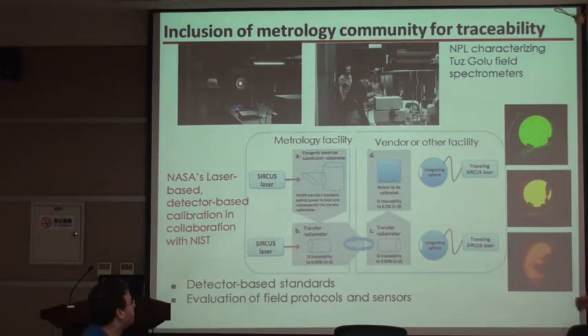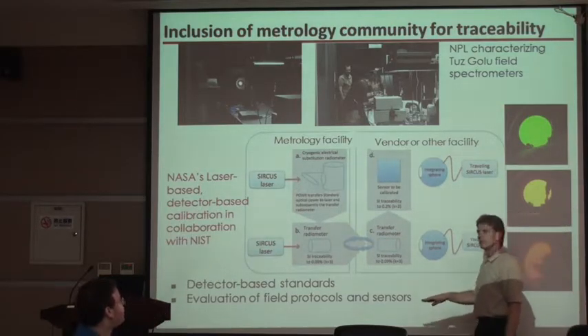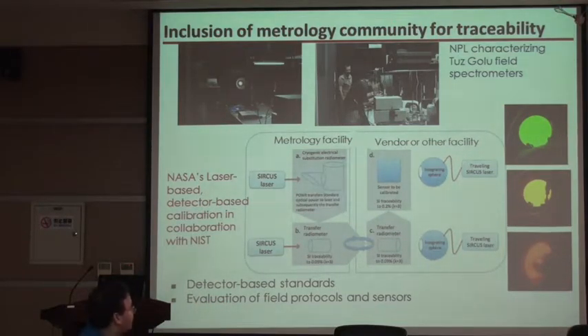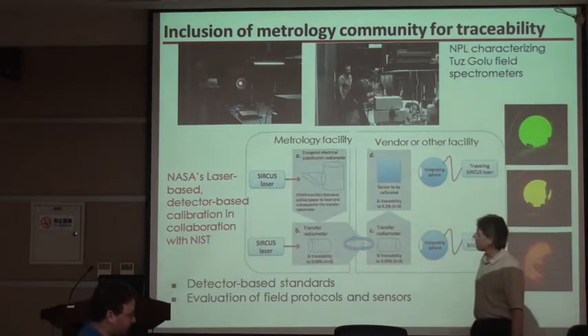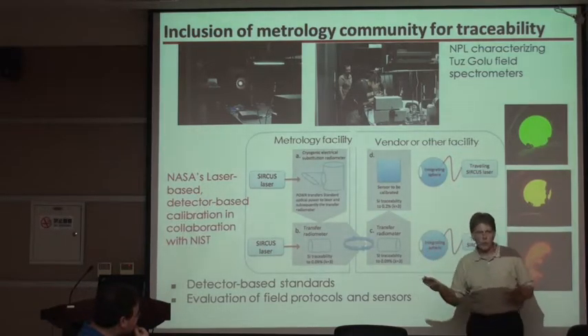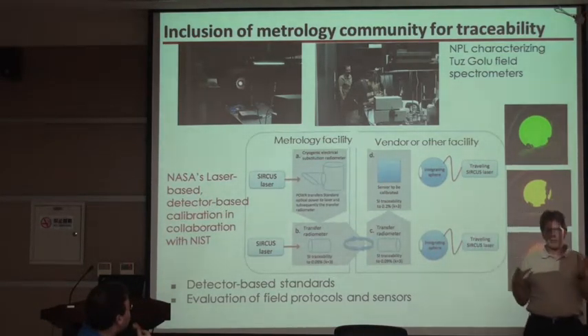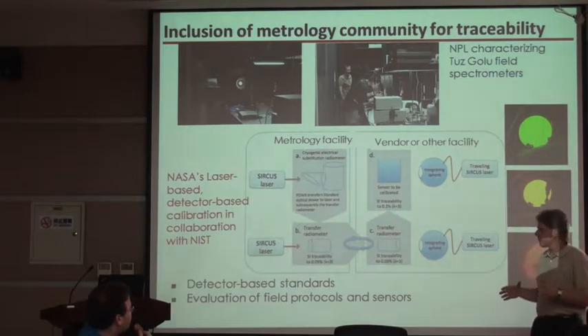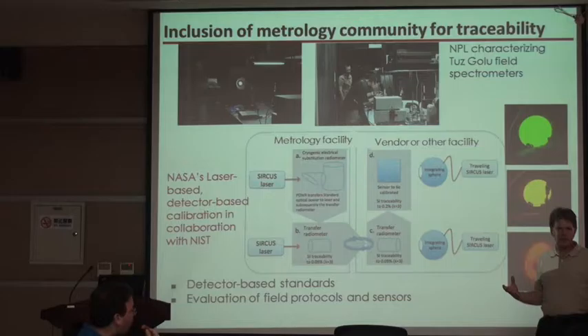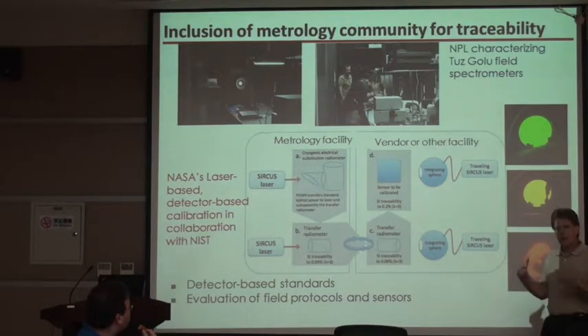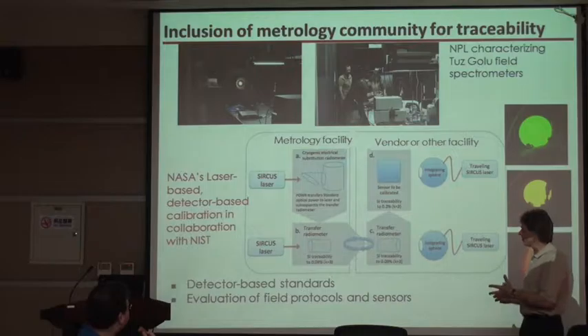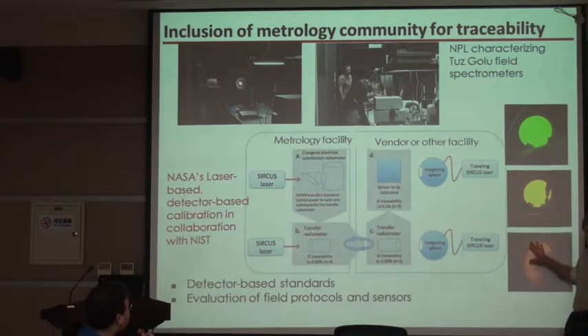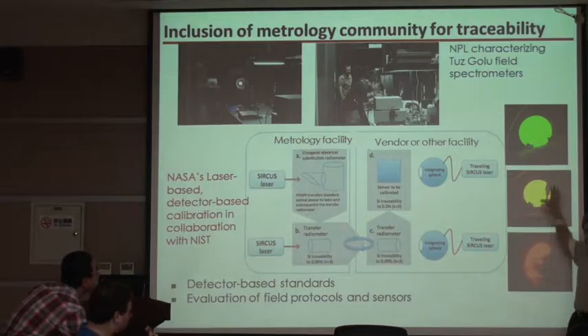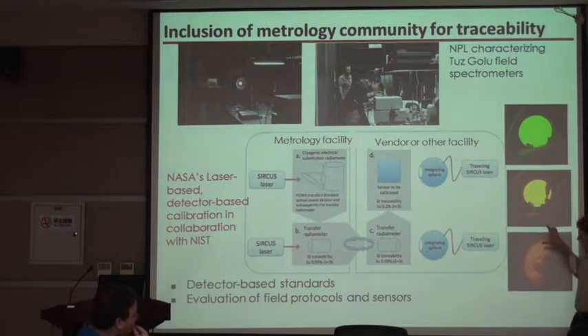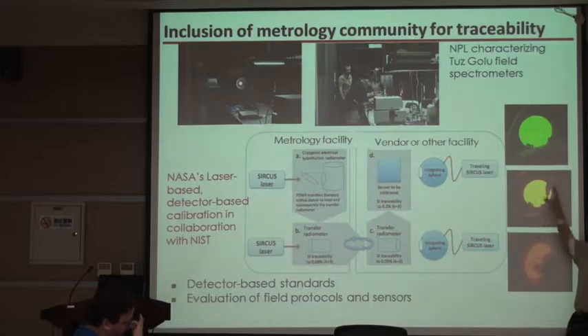What I had talked about a little bit ago was using detectors, trying to get to where we have a better way to calibrate instruments in general. The way we started doing it is something called Circus, which was a NIST-based activity. National Physical Laboratory has a similar system. Instead of using broadband light, it uses tunable lasers. The problem is still understanding what the output of that tunable laser is.